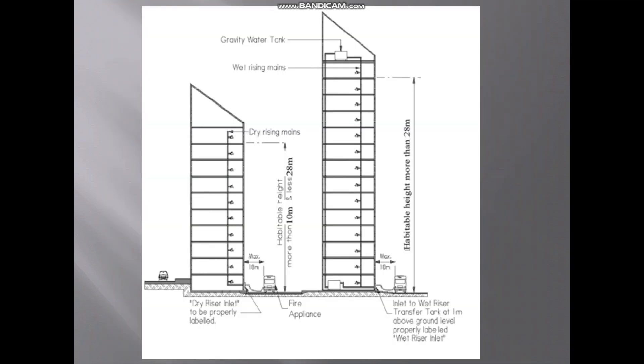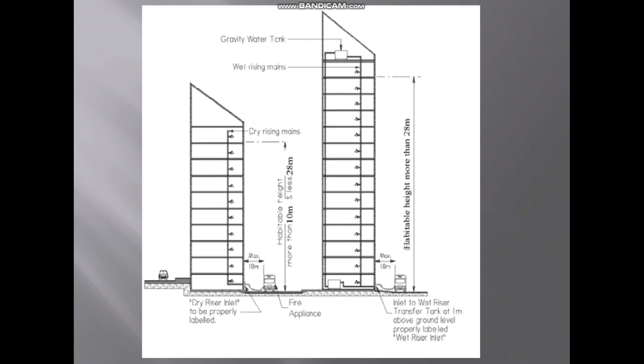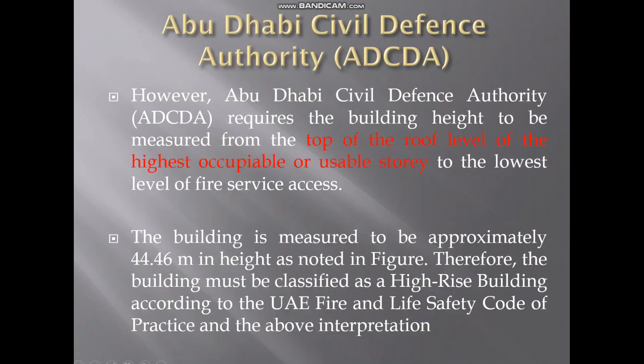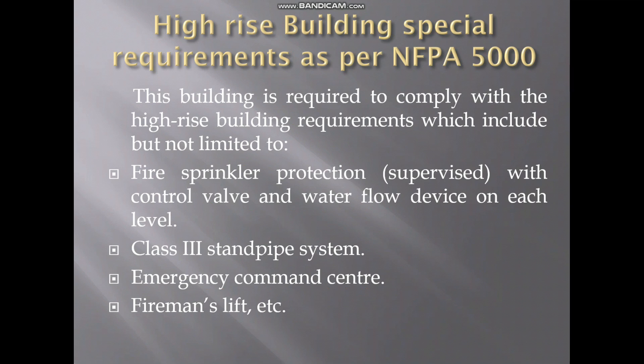Each building type has different requirements. For high-rise buildings, I have highlighted some key requirements. Mainly, you need fire sprinkler protection at each level with a supervised control valve and water flow device — that is the zone control valve — and we need a Class 3 standpipe system.